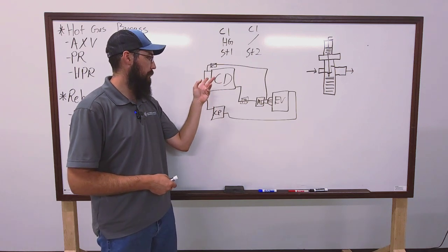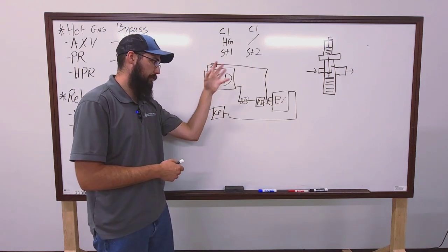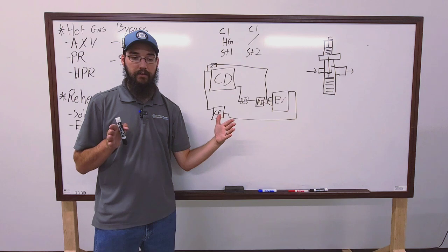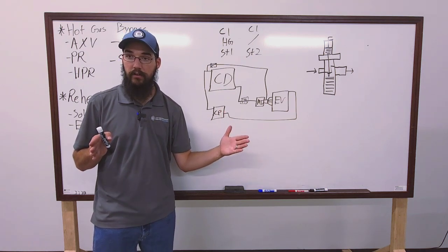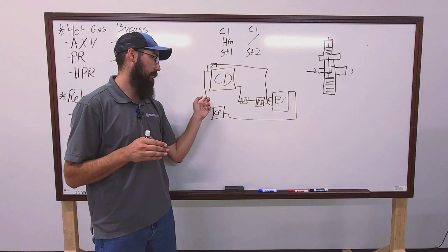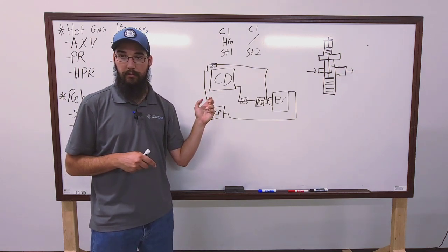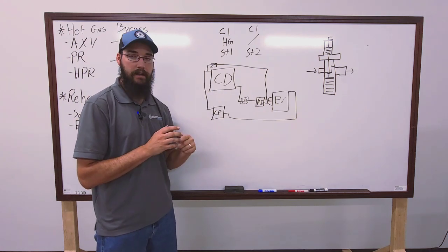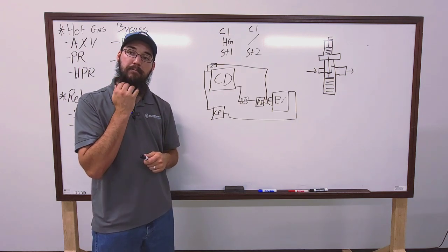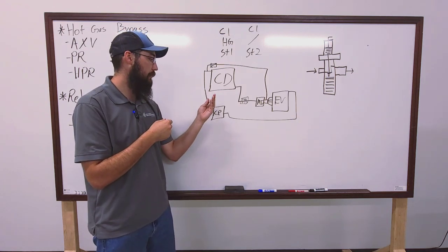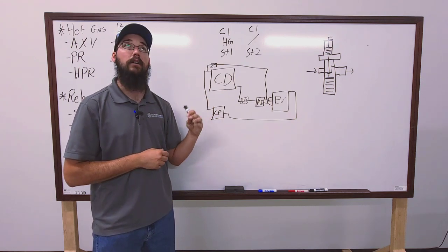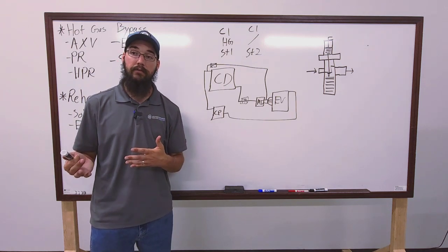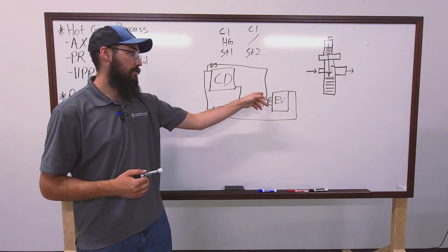I mean, yeah, they're... A lot of them will be. Right. Like... Tranes are inside the actual lower cavity, no? No, they're outside of the condenser. Yeah, the IntelliPak, there'll be a line. I drew it way up here just for the sake of my drawing. Right. But in reality, they're usually within... In terms of line set, they're usually within a few feet of the discharge line coming out of the compressor. There'll be some sort of T or some kind of takeoff coming off of it, and it's going to be pulling straight hot gas. Right. Where the actual valve is located, though. Usually, that'll be close to the compressor. Right. I'm trying to think of if I've seen one close to the EVAP. I don't believe I have.